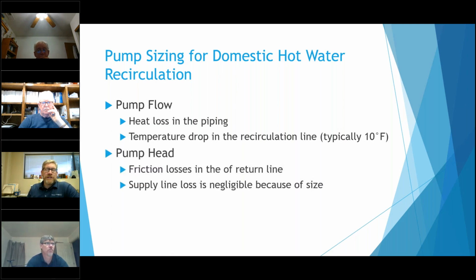The pump head, you just have to really worry about the friction loss in the return pipeline. The reason for that is the supply line might be 2-inch, and you're only bringing 1 GPM through, and the friction loss on 1 GPM in 2-inch pipe is very, very negligible. The friction loss factor is like 0.0001. It's so low that just a little portion of the safety factor will get it through the supply line. So you just have to worry about the length of that return line and whatever that is, and they would figure up the friction loss through it.